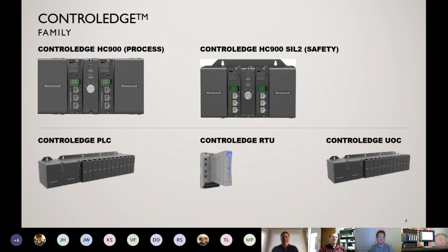The ControlEdge RTU, which is in the lower middle, this is for applications where you might need a remote termination unit out in the field to accept inputs and provide outputs to a process like a pump house. It could be a remote pumping station, a remote skid gas train. A lot of different applications where you just need an I/O rack out at the process to be able to do some of your process control. It really allows for quick and easy addition to I/O out in the plant where you might have hard to reach areas where you don't want to add a full PLC or a hybrid control at one of those processes.